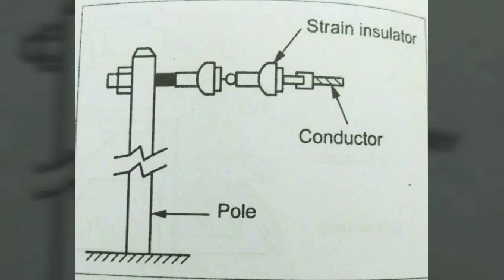Next, strain insulators. These insulators are used to take the tension of the conductors at termination of the line and at angle positions where there is a change in direction of the line. For light low voltage lines, a shackle insulator is suitable, but for higher voltages, a string of suspension insulators is necessary.